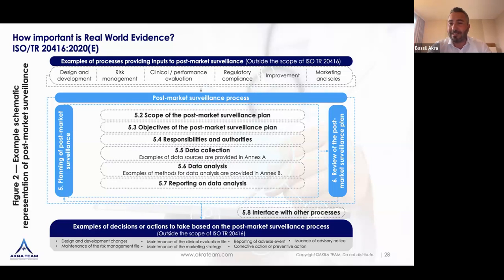A lot of manufacturers are still struggling with the initial risk that they have defined, the acceptance criteria for the risk management file, where they set it actually at the development phase, but they never fed back with data from evidence on a post-market level. This process has to ensure that there is a connection between risk management, post-market, and clinical. They need to talk to each other. And if they are talking to each other, but they are not getting data from a post-market level, your risk estimate could be wrong today because you didn't consider those data.